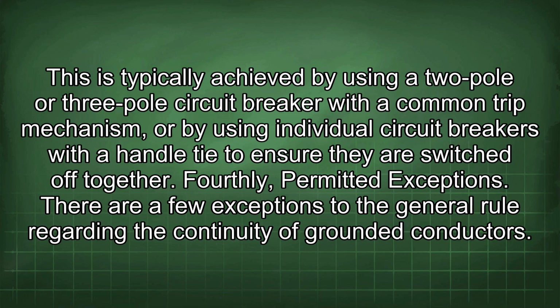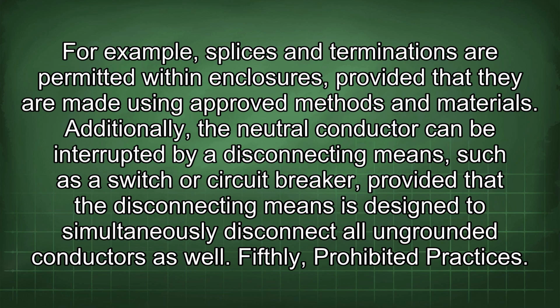Fourthly, permitted exceptions. There are a few exceptions to the general rule regarding the continuity of grounded conductors. For example, splices and terminations are permitted within enclosures, provided that they are made using approved methods and materials. Additionally, the neutral conductor can be interrupted by a disconnecting means such as a switch or circuit breaker, provided that the disconnecting means is designed to simultaneously disconnect all ungrounded conductors as well.